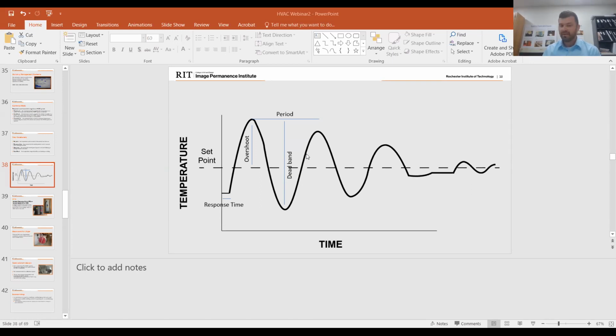Okay. Are you likely to have problems switching the air handling unit on and off as needed, or are they designed to run continuously? Is the air handling unit designed to turn on or off, or is it designed to run continuously? That comes down to your unit as well. We have worked with older air handling units, and I'm talking mid 80s, not very old, that was on a BMS system that could not be shut off whatsoever. If you shut it off, it erased all the computer programming and it had to be redone from scratch. But we have also worked with units from the 60s that were modified to BMS that could be turned off and on routinely. It's definitely something to work with your facilities on. That's the process we have in the methodology as well, but it's definitely something to look into.